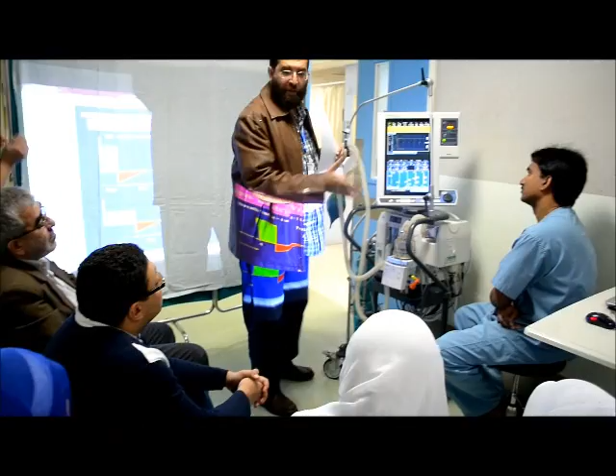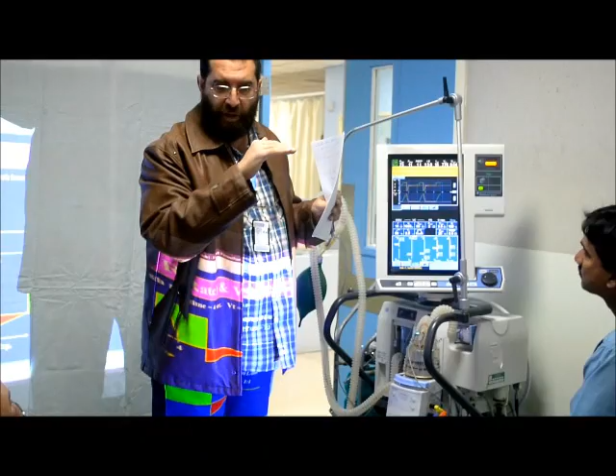Now I increase the peak alarm to avoid that it will abort the cycle. You know the alarm level. If I put the peak pressure at a certain value, and the pressure reaches that value, it will not deliver the whole tidal volume. It will abort part of it to avoid exceeding that pressure, which is the limit for the alarm.